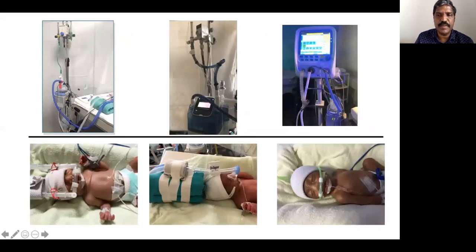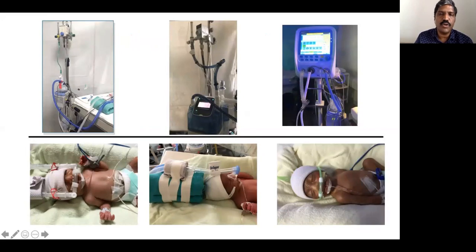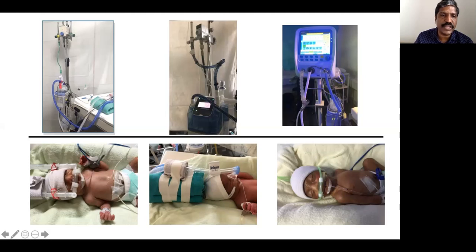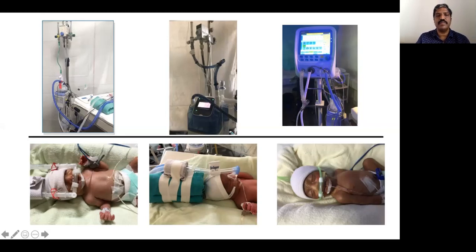Bubble CPAP requires a compressed oxygen source, compressed air source, a blender, a flow meter, and a humidifier delivering warm humidified gases through the inspiratory limb to the patient, with an expiratory limb dipping into the bubble chamber. In a ventilator-based CPAP, an obstructive valve on the expiratory limb generates pressure instead of bubbles. Any of these machines can be used with an appropriate interface.